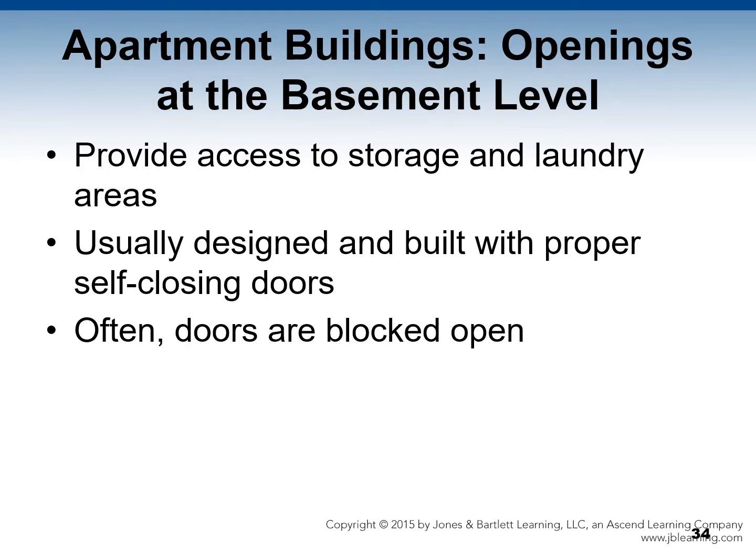Then you have openings at the basement level. These provide access to storage and laundry areas. They're usually designed and built with proper self-closing doors. But often, unfortunately, doors are blocked open. And I'm sure you've been somewhere, and maybe even in your own building at some point. You see a sticker on the door that says, "Fire door, do not block or prop open." And there it is, blocked or propped open.